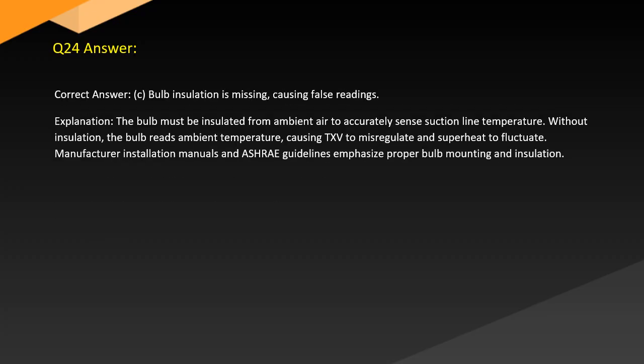Answer. Correct answer: C. Bulb insulation is missing, causing false readings. Explanation. The bulb must be insulated from ambient air to accurately sense suction line temperature. Without insulation, the bulb reads ambient temperature, causing the TXV to misregulate and superheat to fluctuate. Manufacturer installation manuals and ASHRAE guidelines emphasize proper bulb mounting and insulation.